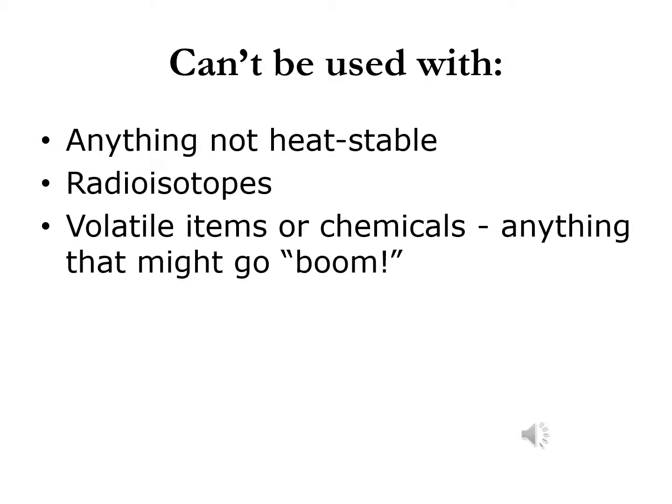So here are two important takeaways from this presentation. To check the function of an autoclave, you need to know how long the autoclave kept the items at a certain temperature. At least 15 minutes at 121 is generally the temperature and time you want. And the second thing is, and this is important, not everything can be autoclaved.